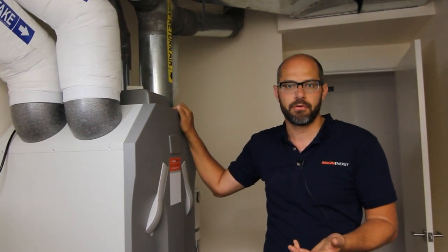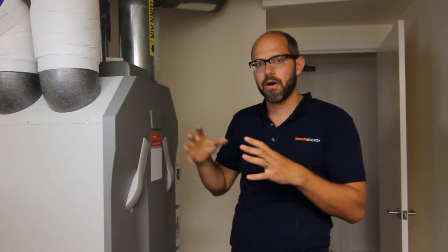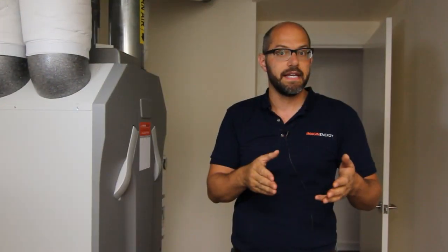That's a bit of an unusual approach for a passive house. Overall we're kind of stretching the boundaries of a couple of different pieces of equipment. For instance, a normal heat pump that we would want for this house doesn't get small enough to be able to handle how low the heating and cooling needs are for this passive house. It really uses very little heating and cooling. We would normally use that typical American heat pump, but they just don't come in sizes small enough.